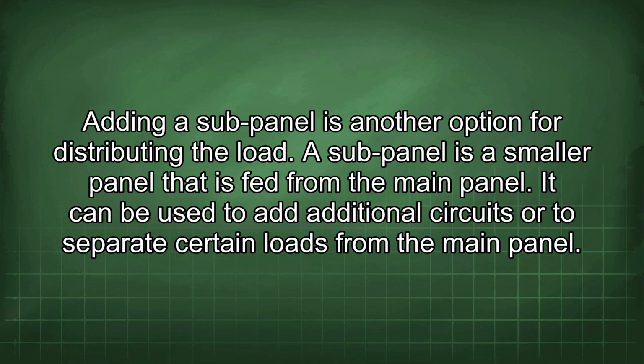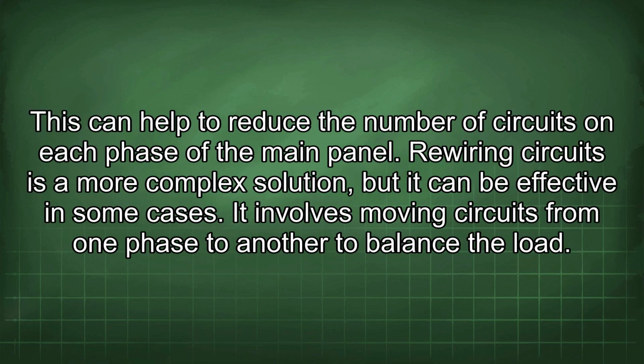Adding a sub-panel is another option for distributing the load. A sub-panel is a smaller panel that is fed from the main panel. It can be used to add additional circuits or to separate certain loads from the main panel. This can help to reduce the number of circuits on each phase of the main panel.